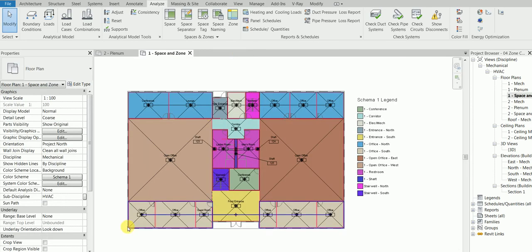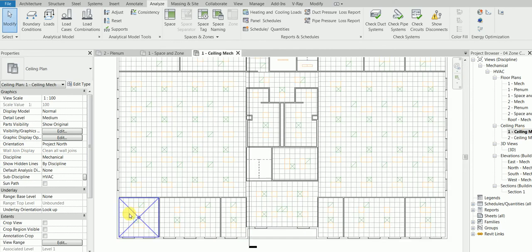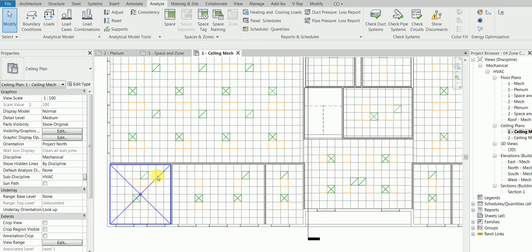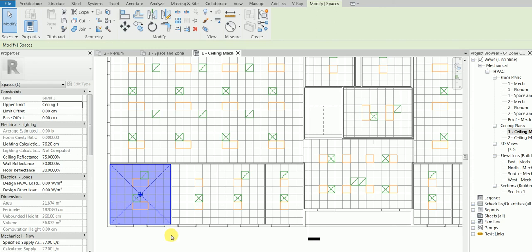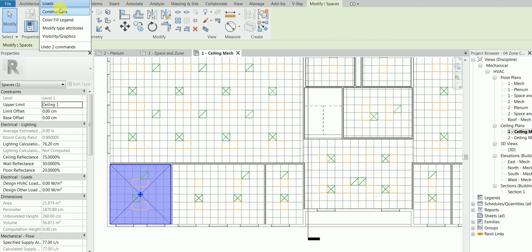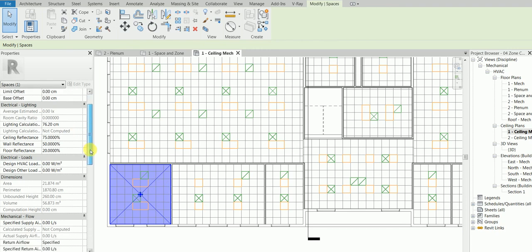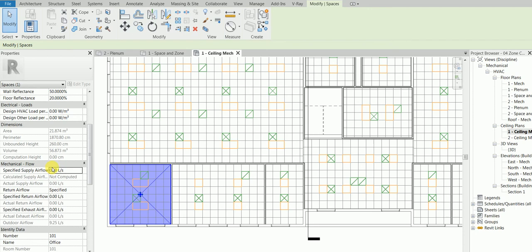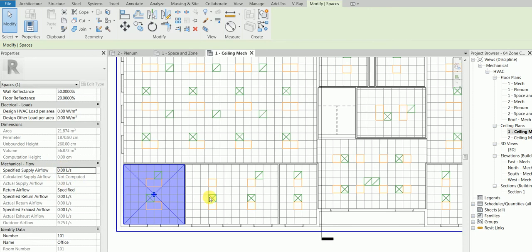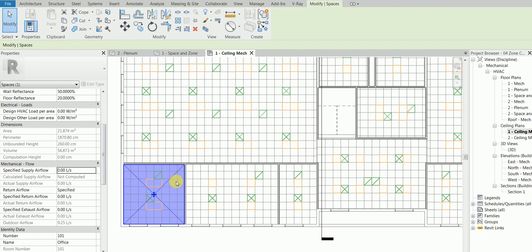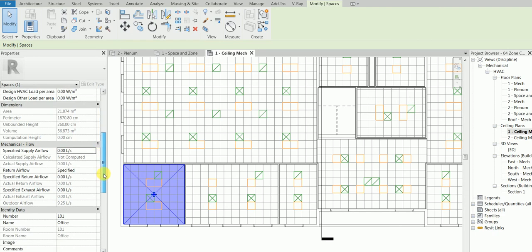Now, why did we do this? Let's go to the ceiling plan. For a given area, if I want to place air terminals, I need to know the calculated supply airflow for that space. Before running the calculation, this value shows as 'Not Computed.' Once we run the load calculation and place an air terminal, the airflow is based on the calculated supply air value. This is why we do the loads — don't worry, it's straightforward.